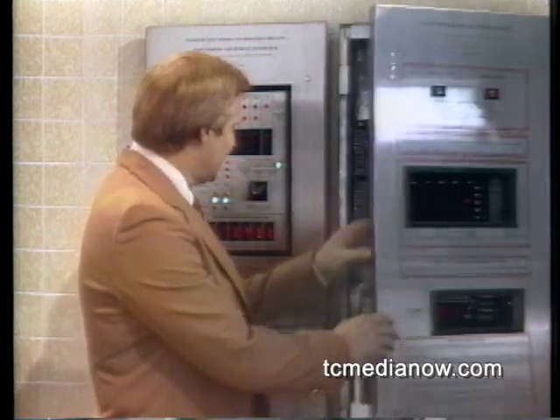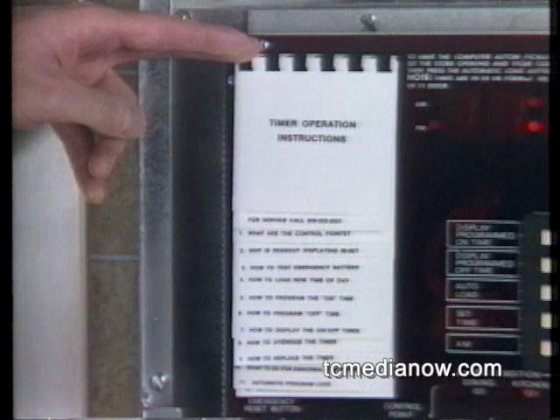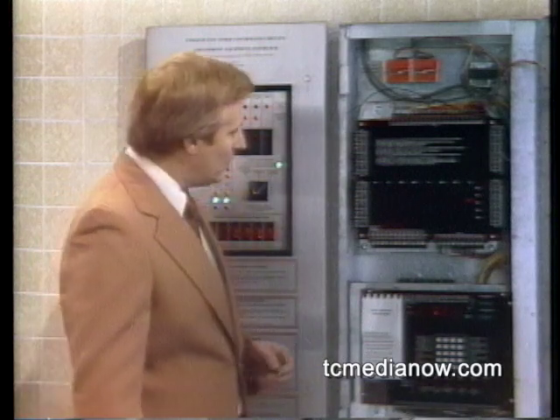Even though the system runs automatically, there may be times you want to manually override one or more of the functions. A booklet fastened to the clock gives you all the time cues in the auto load program and also contains simple instructions on how to customize the program to fit your store's individual needs. If you simply want to change the store's opening or closing time, all you need to do is change the opening or closing thumb wheel settings and press the auto load button. The auto load program automatically adjusts to the new schedule.